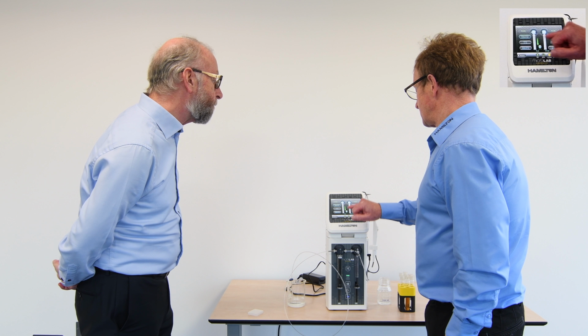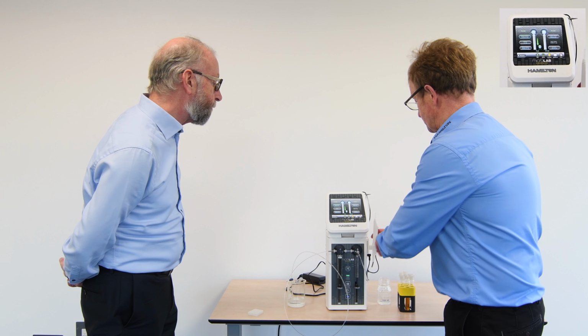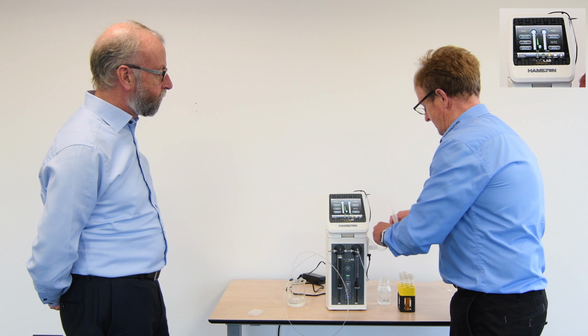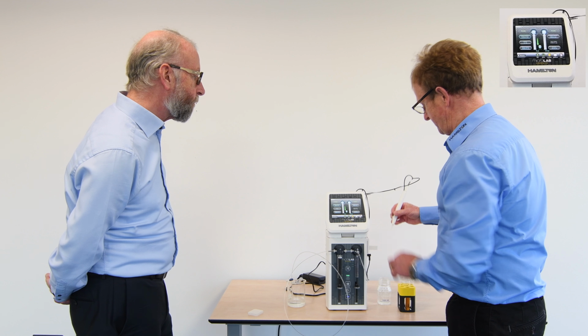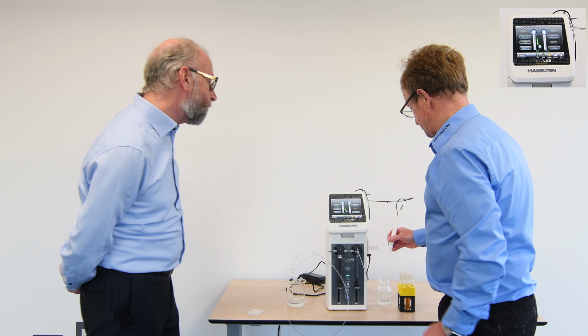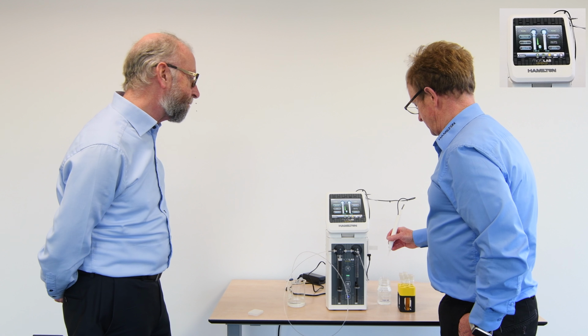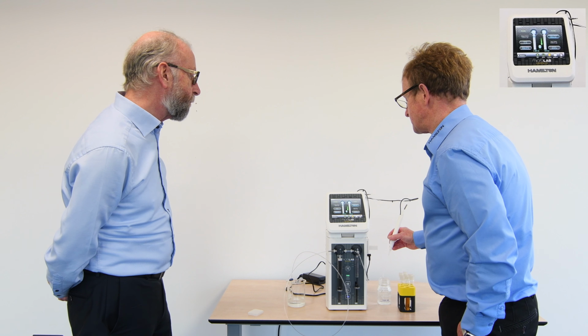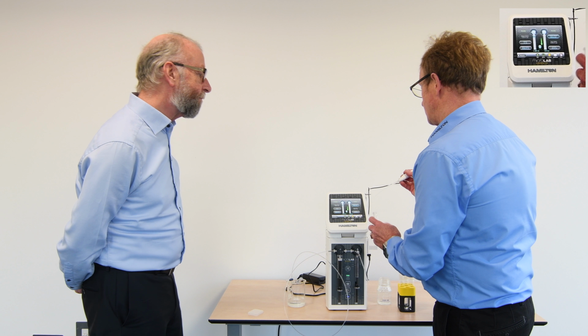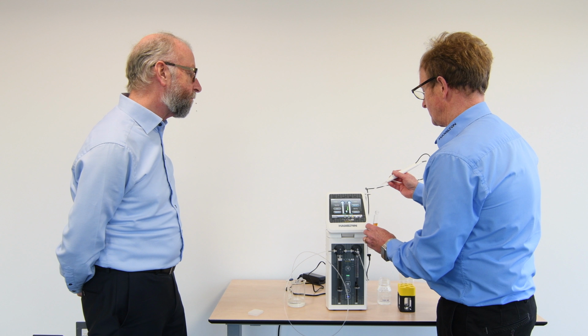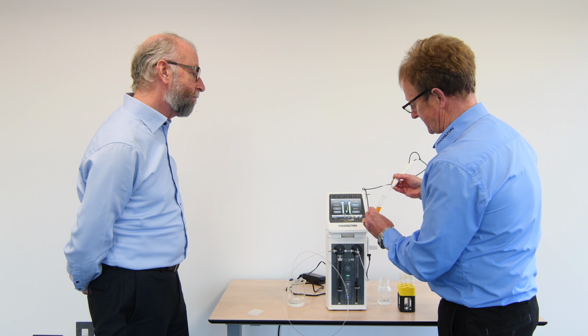And we're going to conduct the same sort of program as we had before. So if we activate that program by, again, using the button on the hand probe, you'll see the first stage it's going to do is aspirate our diluent, which is taking up that 1500 microlitres. The next stage, it took up the amount of air gap, you see automatically here, and now it's going to pick up our sample here, 500 microlitres.